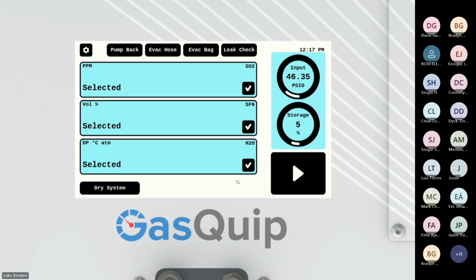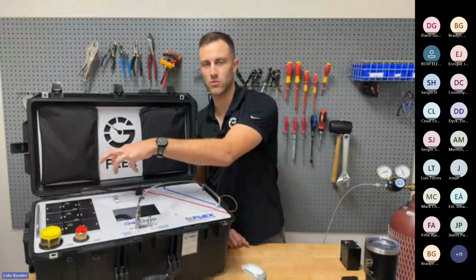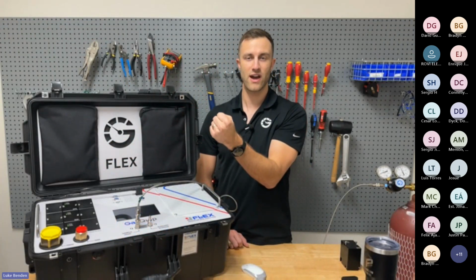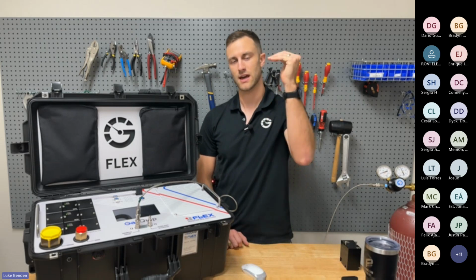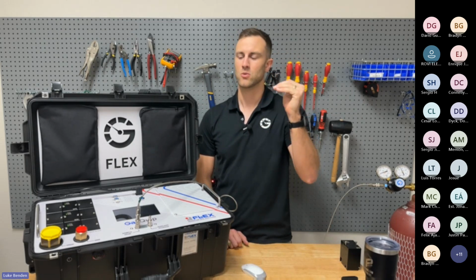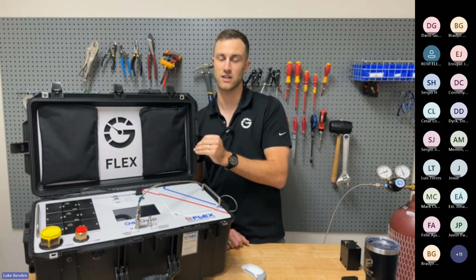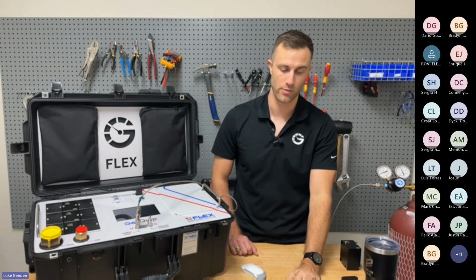Now let's talk about some of the functions. Like I mentioned earlier, we've already run the evacuate hose function. The evacuate bag function is, say you're running nitrogen through the device to flush it out, and you have a device full of nitrogen. You can just flush that out of the device to ambient air with the evac bag function. Leak check, this would be a vacuum pull on all of the internal components. So it pulls a vacuum on all the internal modules, plumbing, and it'll hold that vacuum for 30 seconds to see if any vacuum rise happens inside the system. And if it does, then you know you have a leak, which could be causing some of the issues you're seeing if you're getting high or low readings, depending on which module you're talking about.